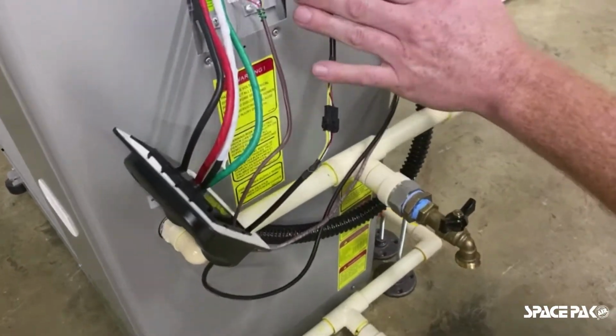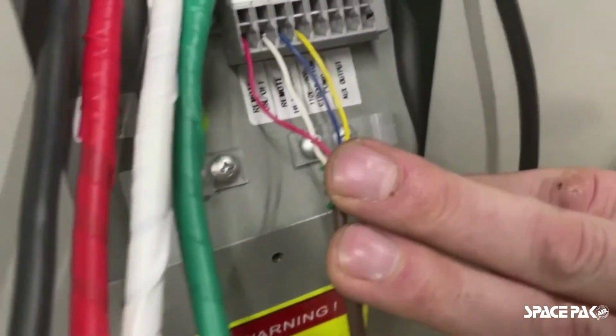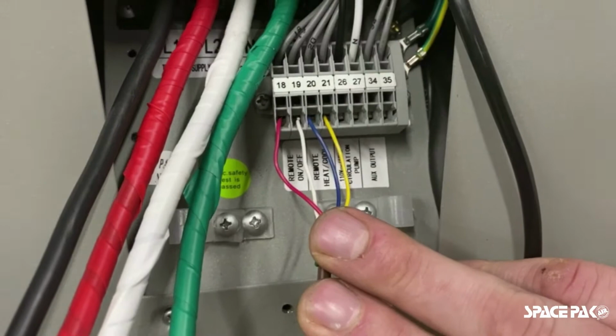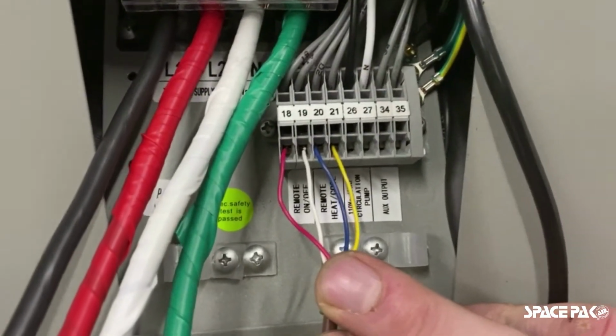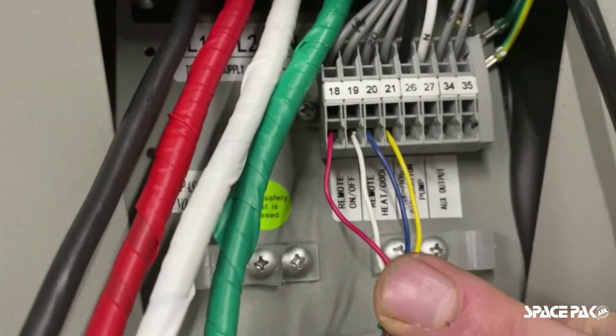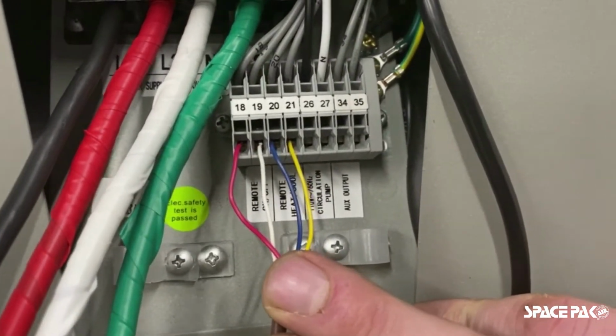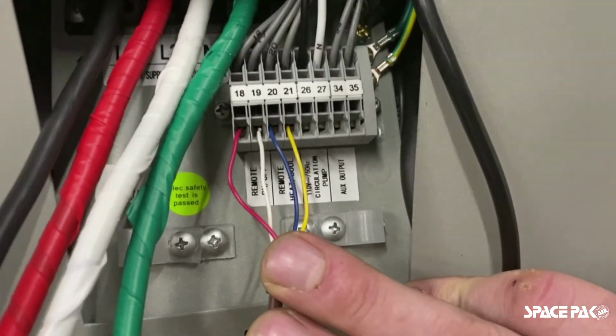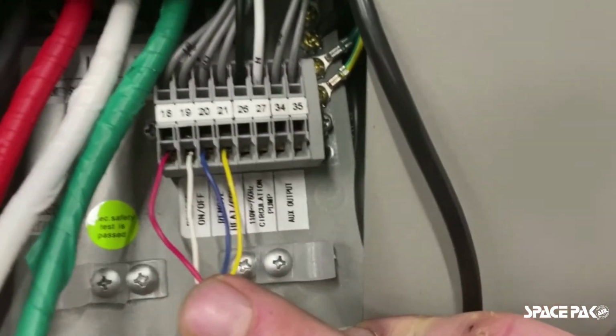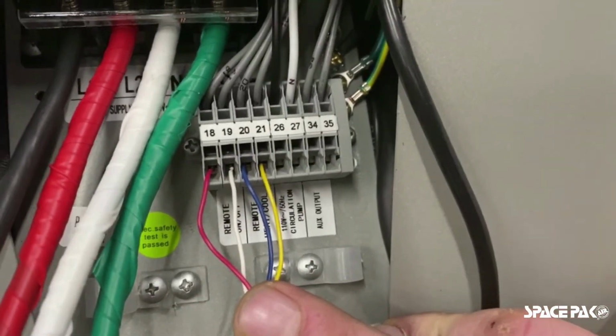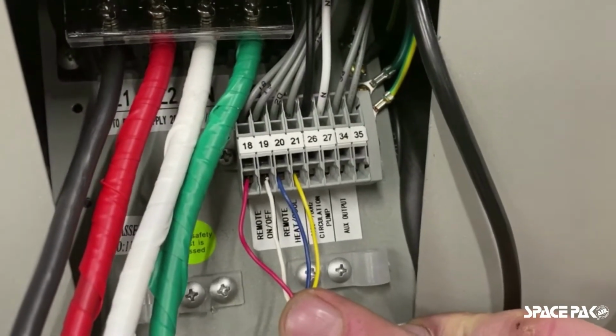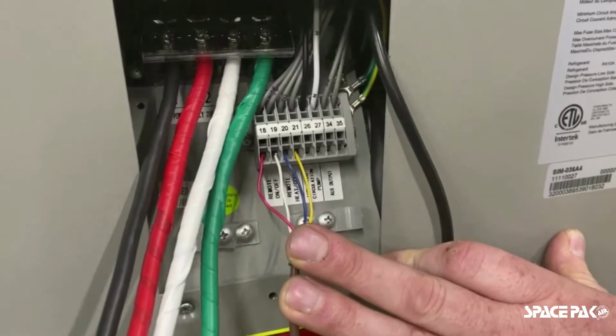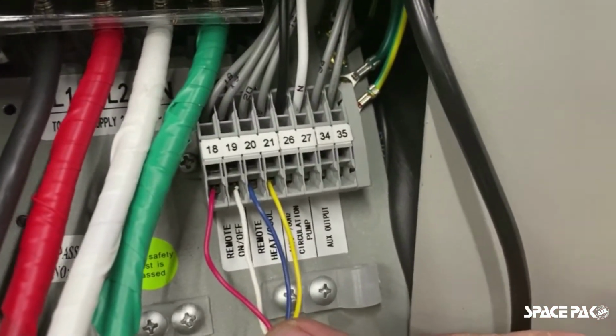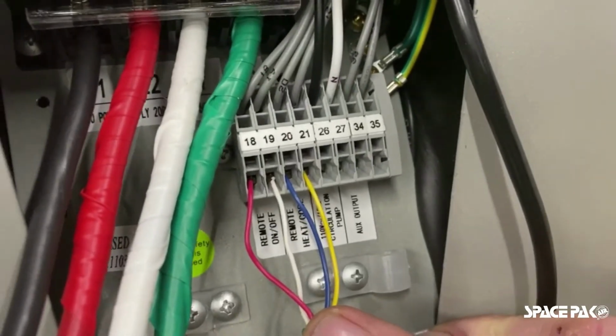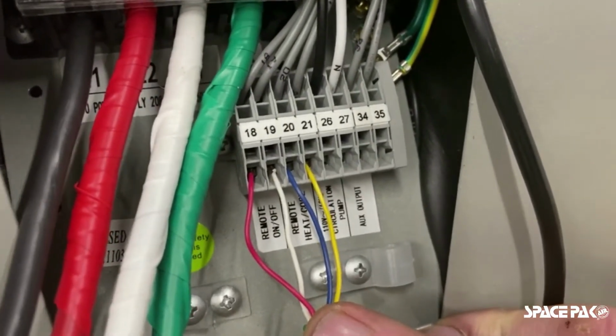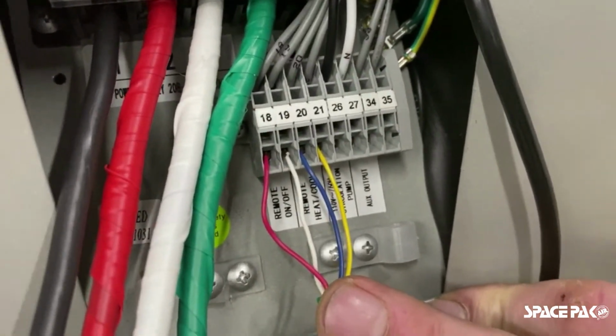Now, if we go to the low voltage control side, you can see that we've landed 4 18-gauge wires, 2 on the remote on-off and 2 for the remote heating and cooling. So just as they explain, an open and close on terminals 18 and 19 will decide if we're going to be on or off with the unit. And then an open and closed on terminals 20 and 21 will also say if we're going to be in heating or cooling mode. Now this particular unit, closed would be in heating mode, and open contacts are cooling mode. So if something ever happens to a wire, it would actually fail open or fail into the cooling mode. So that's something to be aware of.